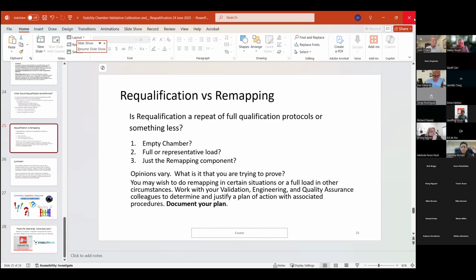For the number of sensors, or for just the overall? Well, let's say they had a number of sensors in order to have continuous mapping, let's put it that way for the start. Yeah, I would say if you had multiple sensors throughout the location within the chamber that the chamber was initially validated at, if you had sensors representative of those, you'd consider that your ongoing validation. You have a continuous ongoing validation, so the chamber would technically always remain in the validated state.